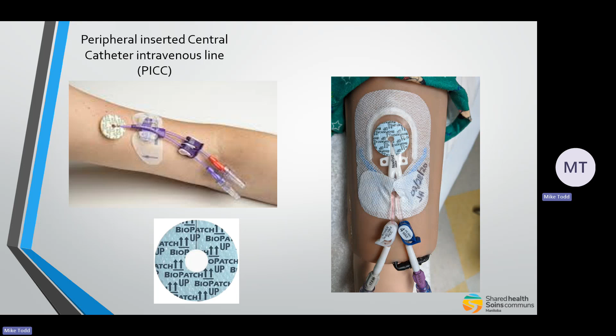Other components of our PICC line: we have the clamp itself. When the line is not used, the line should remain clamped. That way it prevents blood from draining out of the line. Some of the lines may not have this clamp in place, but they have a valve inside the line which prevents blood flowing out of the tube. If you're going to be doing this, usually in a healthcare setting, because obviously we're not going to be initiating these, talk with the care providers if you don't see a clamp, to check that they have that valve in place to prevent backflow, or maybe the clamp is missing. Just confirm with the caregivers.